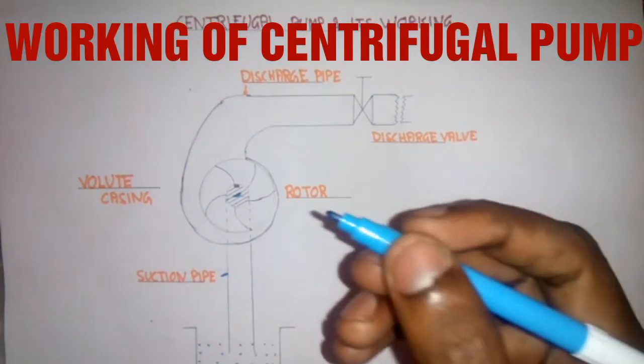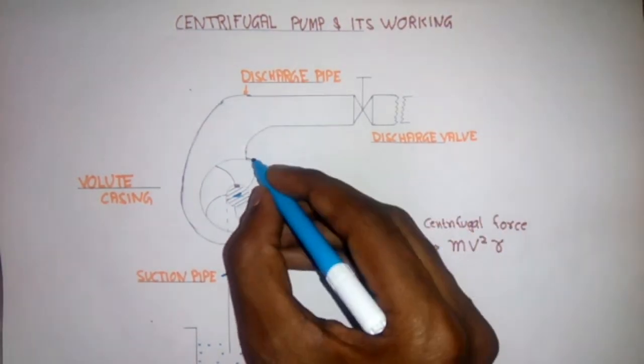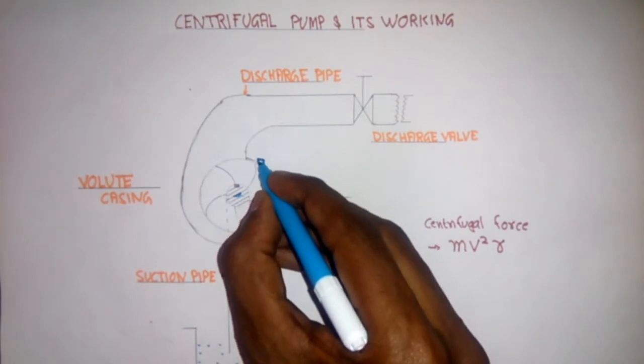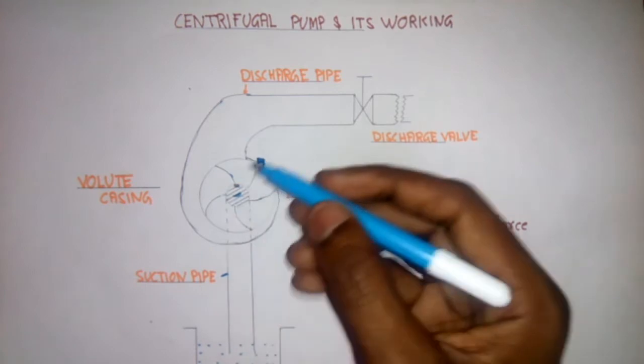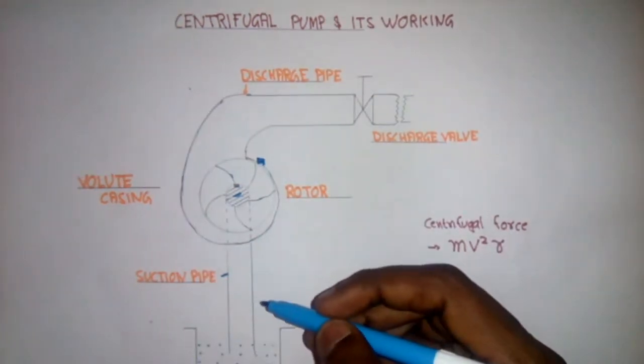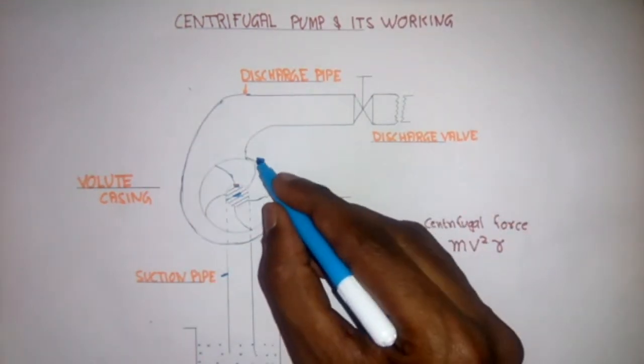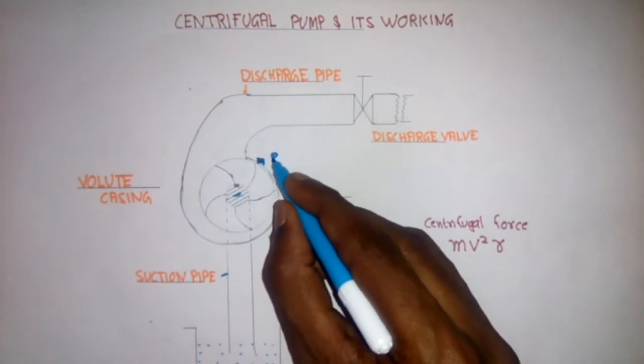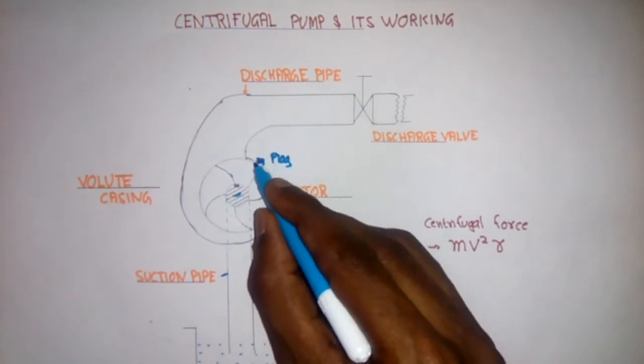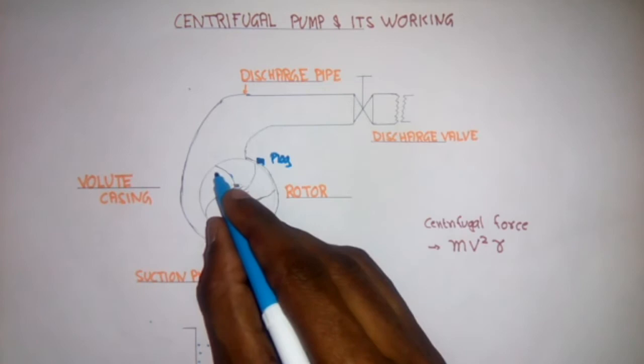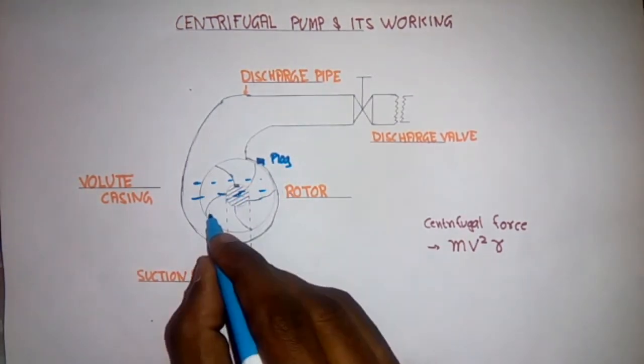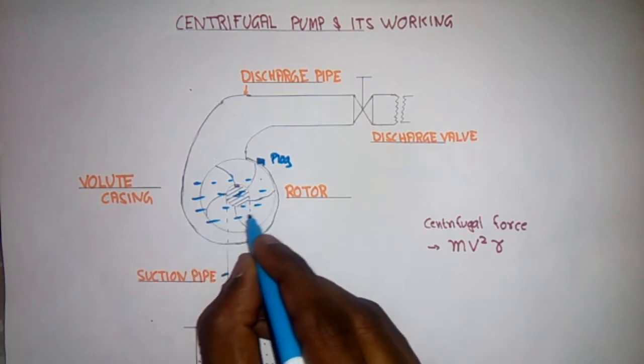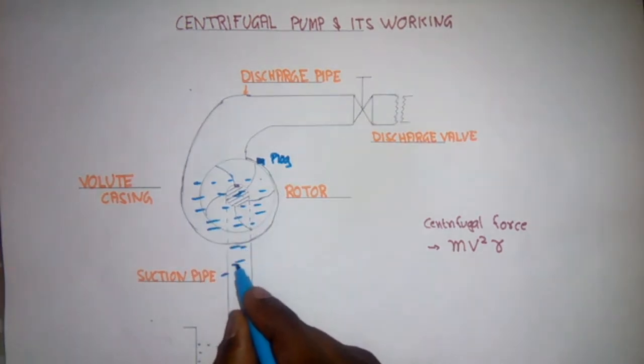As I already stated that the centrifugal pump requires water priming. The priming means its casing and suction side need to be filled with the water. For that we have one plug on casing. We will open that and fill that casing with the water so the air is removed from the casing and the suction side.